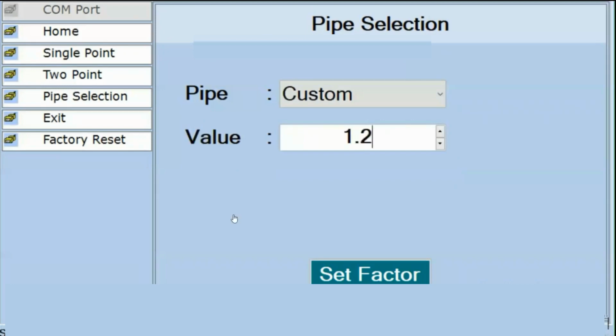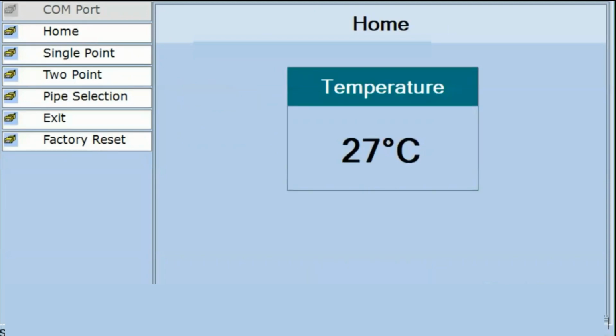In the custom pipe selection, we define some kind of factor. So I will select one thing. You need to adjust the factor here, on-site calibration needs to be done. You need to put the factor from 0 to 5 and check at what point you are getting the exact temperature. If you don't know the material of the pipe and the thickness of the pipe, that's the case. So here it is for any pipe which we have not shown here. You can put the calibration factor here, and then you can get the exact results for that pipe also. This can vary from 1 to 5 and more than that also, depending on the pipe material and thickness. Once you set this, you will get the exact temperature of the fluid inside the pipe. I will show the result of an experiment. Here we have gradually increased the fluid temperature flowing inside an SS316 pipe. So here we are getting the temperature of the pipe.